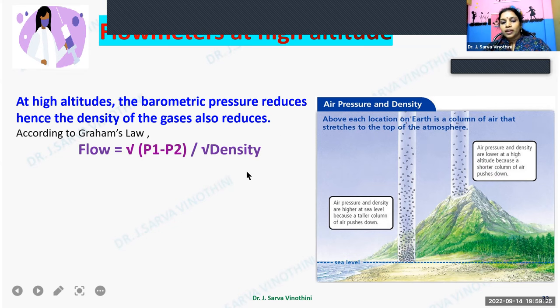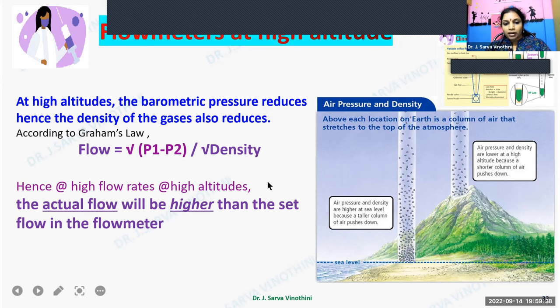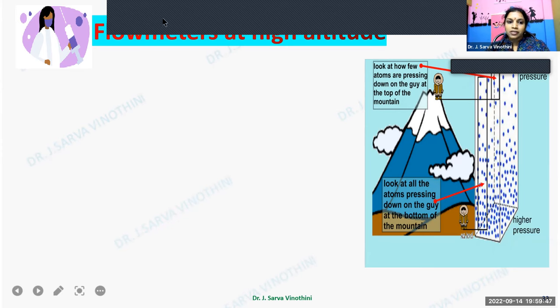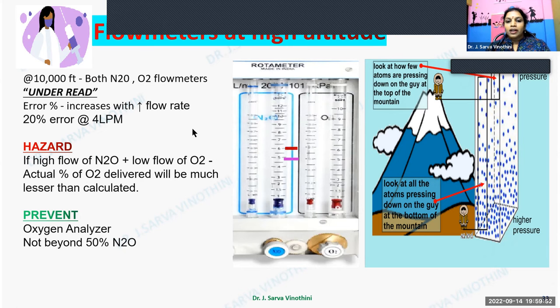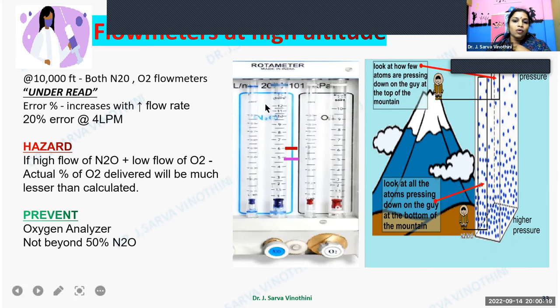At high altitudes, barometric pressure is lower, so gas density is lower. According to Graham's law, lower density increases turbulent flow, so the actual flow delivered is higher than what is set on the flowmeter — the flowmeter under-reads. If using a 50/50 mixture of nitrous oxide and oxygen this is not hazardous, but if using 70% nitrous oxide and 30% oxygen, the nitrous concentration will be even higher, risking delivery of a hypoxic mixture. Therefore at high altitudes it is preferable not to exceed 50% nitrous oxide, and strongly advisable to use an oxygen analyser.